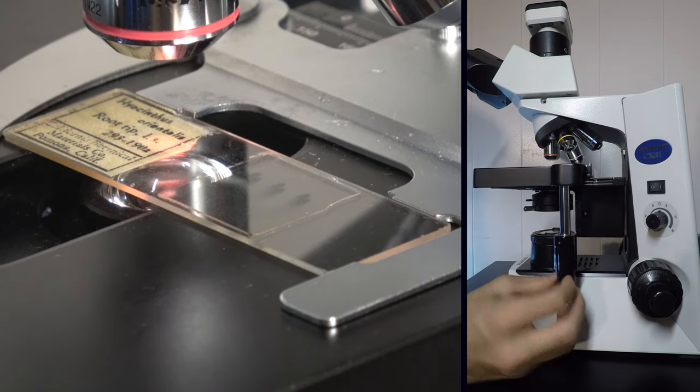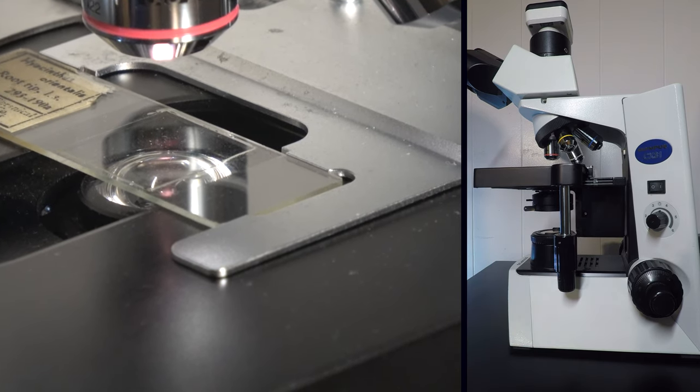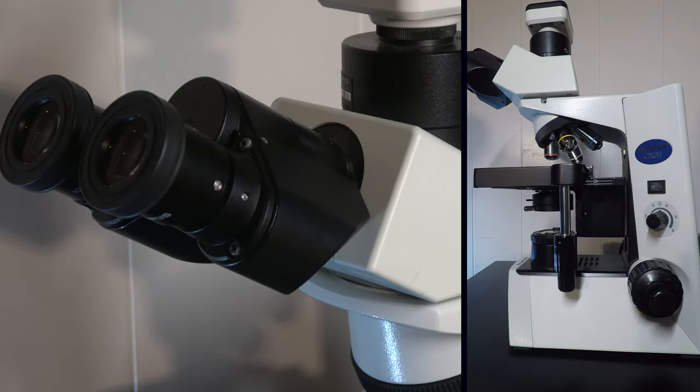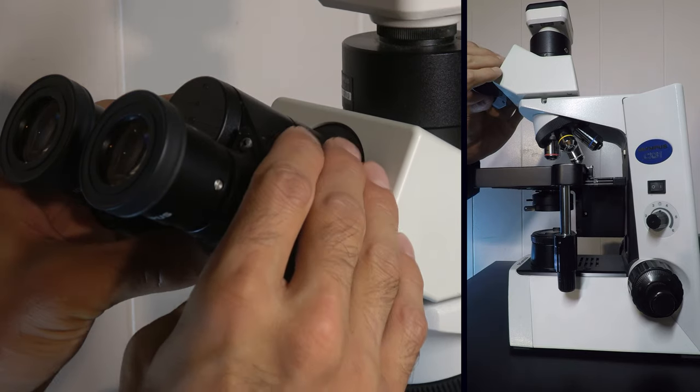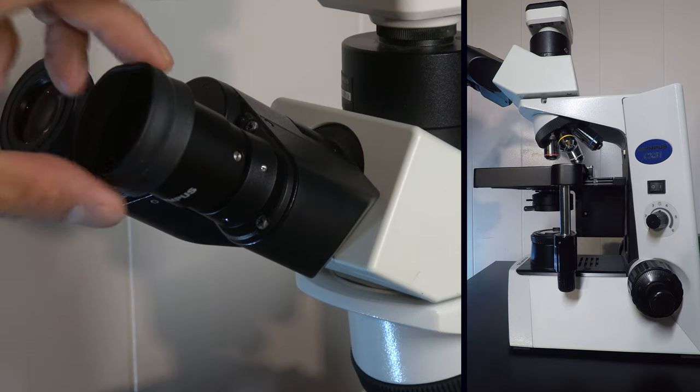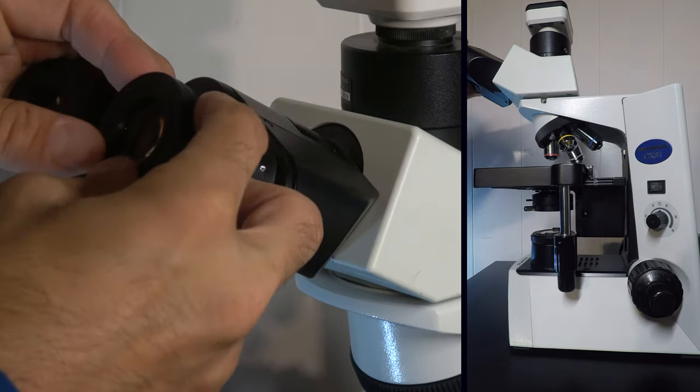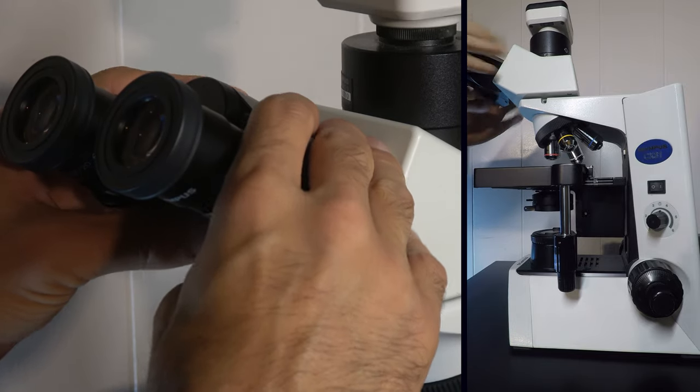Before looking through the eyepieces, use the stage controls to move the slide sample so that the beam of light passes directly through it. Now look through the eyepieces and use the interpupillary distance adjustment to match the distance between your pupils so that you can utilize both oculars. You can optionally fold out the rubber eye cups for increased comfort or to block environmental light.